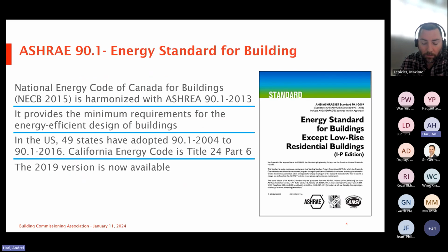Part of this then was that back in around 2007, ASHRAE came up with 90.1, which is an energy standard for buildings. Today, the National Energy Code of Canada for buildings, NECB 2015, is harmonized with ASHRAE 2013, and it provides the minimum requirements for the energy efficient design of buildings. In the US, 49 states have adopted anywhere from 2004 to 2016, and California has its own Title 24, Part 6. Currently the codes are moving to 2019, but I believe ASHRAE is going to be issuing 2021 or 2022. I'm not sure about that.